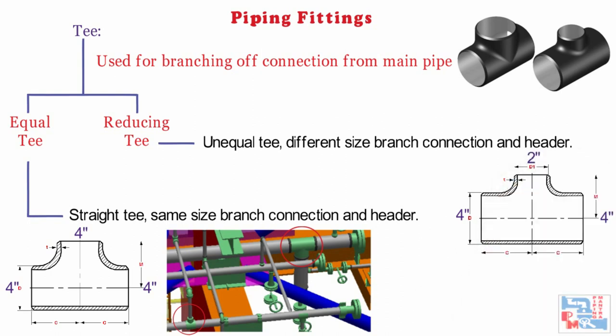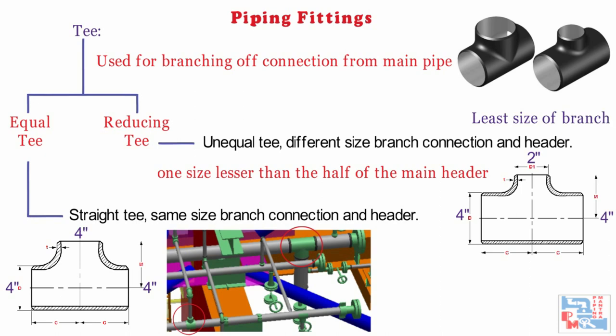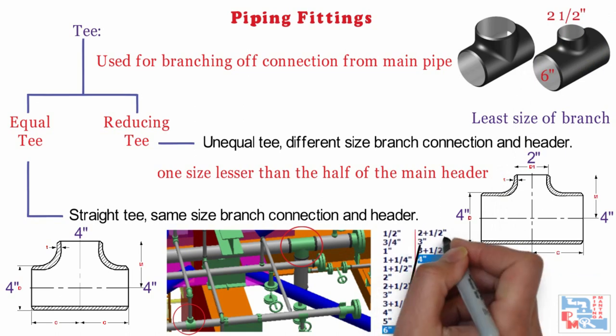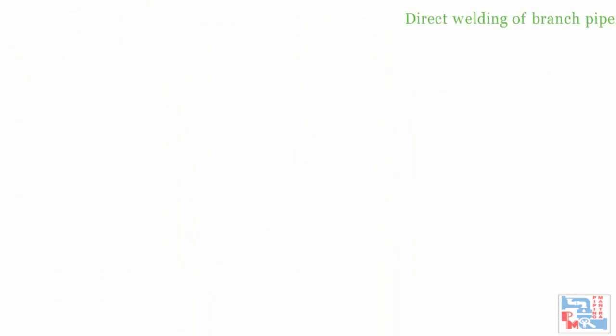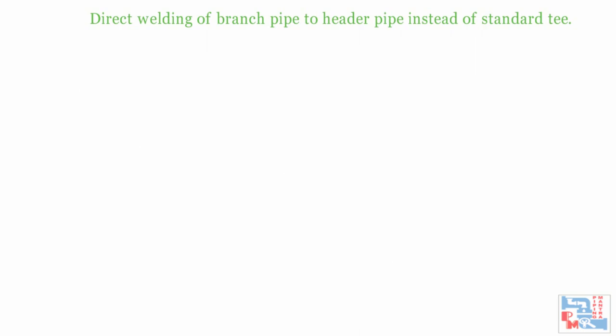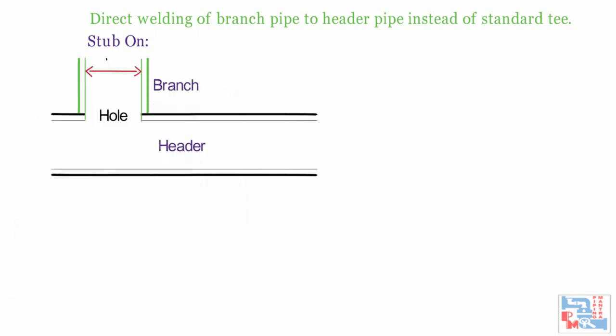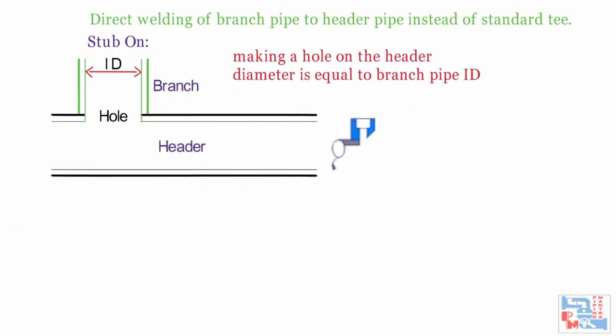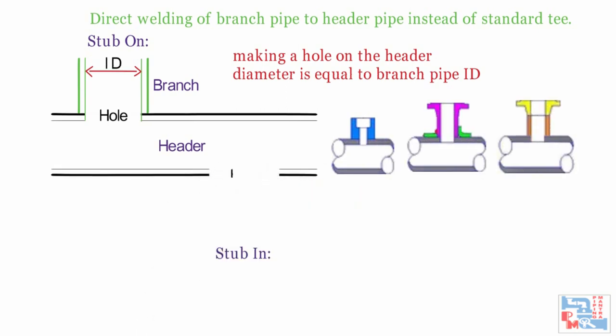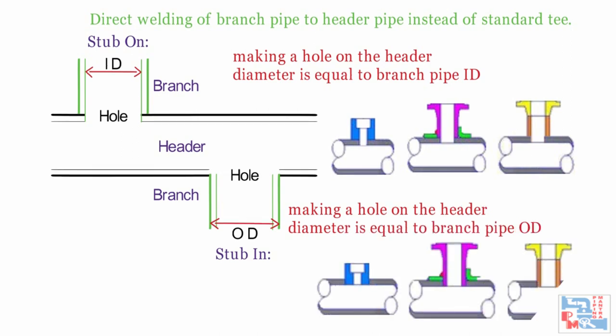Reducing Ts available in the market are one size lesser than half of the main header. For example, the least size of reducing T available for a 6-inch header is 6×2½×2, as half of 6-inch is 3-inch and one size less is 2.5-inch. For low pressure services, branching is done by direct welding of the branch pipe to the header instead of using a standard T. There are two methods: stub-on, made by cutting a hole in the header equal to the branch pipe ID and welding them together; and stub-in. The branching difference between stub-out and stub-on can be clearly seen on screen.